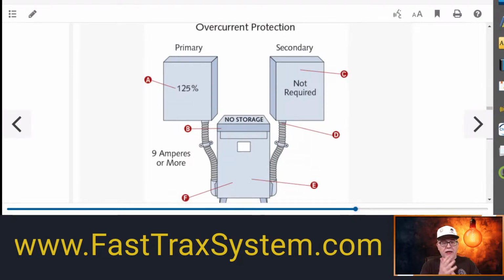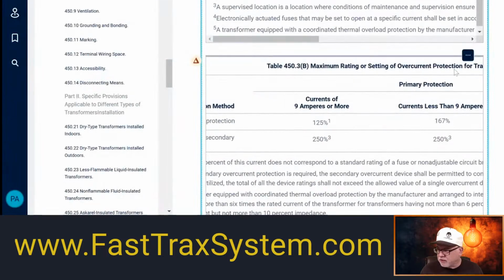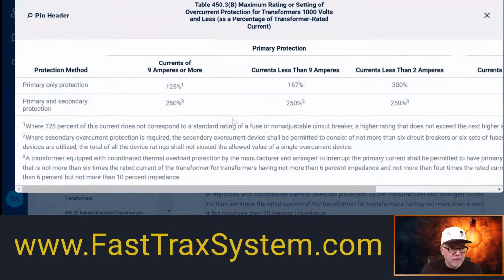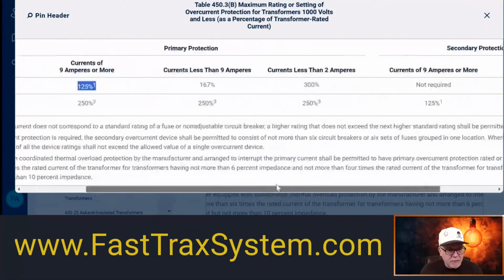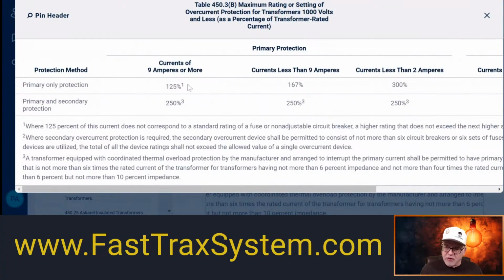So now, if that is the primary protection, let's go to the NEC and see if I can pop this thing out and if it shows it. Okay, good enough. So primary only protection, if that's what we're working with, you notice it says 125%, right? Hold on here. Make sure I can see it. I can't really blow it up any bigger than this or move it, so we'll just move the slide bar. All right, so that's your primary. Notice this little one right here. This little one says, you know what? Ours was 112.76.